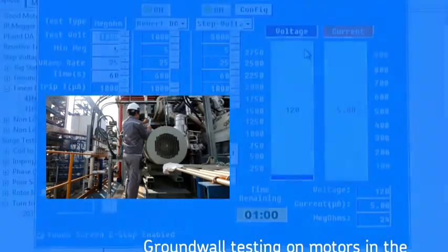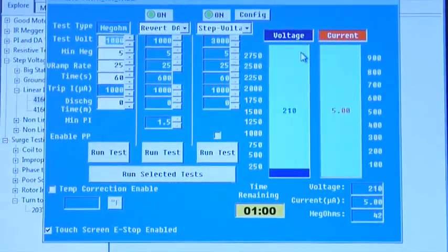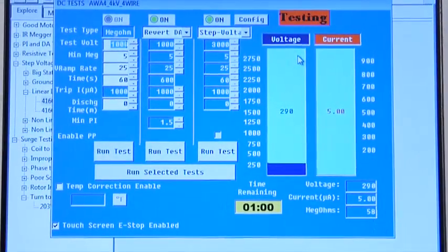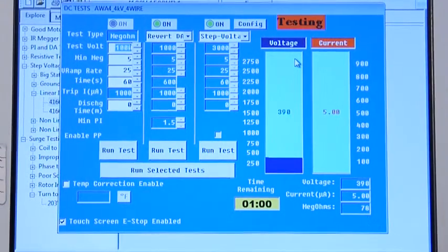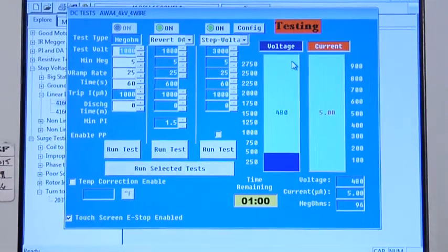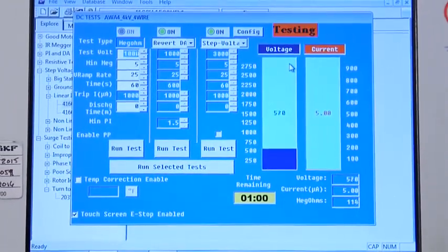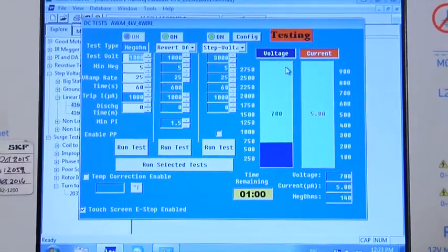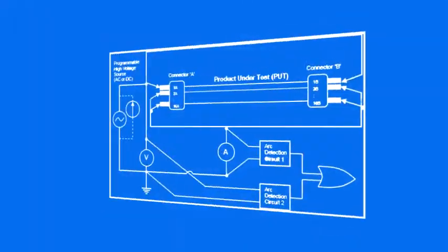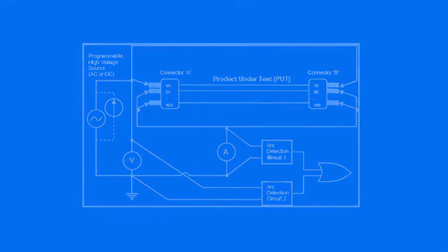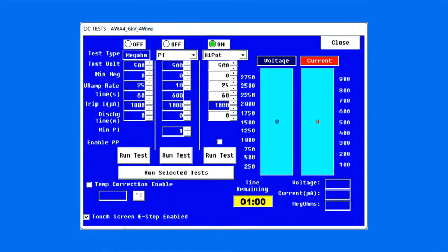A mega test or megohm test typically tests the ground wall insulation at or below the motor operating voltage. This has limited value as insulation breaks down non-linearly as the voltage increases. A hipot test is a DC ground wall insulation test but run at a higher voltage.